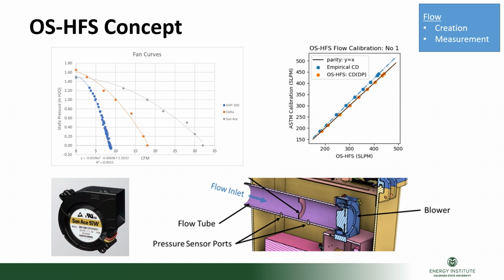So we started off with the GVP 100 blower that was in the Bacharach as a starting point, mapped out our flow curve, and then looked for commercial offerings that would be able to come back in and extend that flow range. We found this Delta fan and the SAN-ACE fan. Once we did a little bit of testing with all of our hoses and attachments on, we found that the SAN-ACE fan was going to be the better choice. So we went with that one and designed around it.